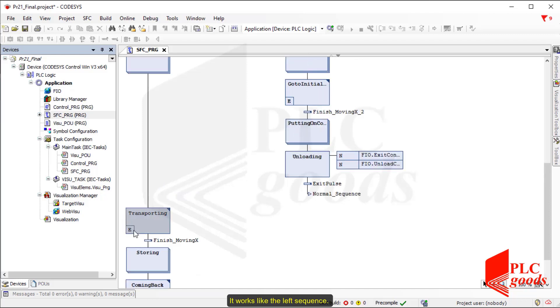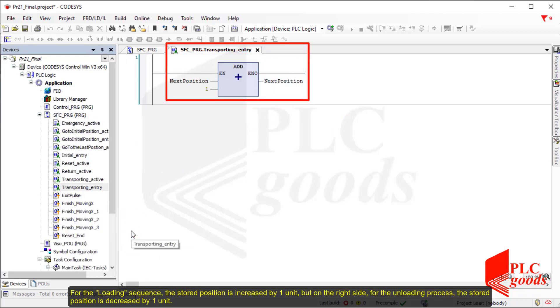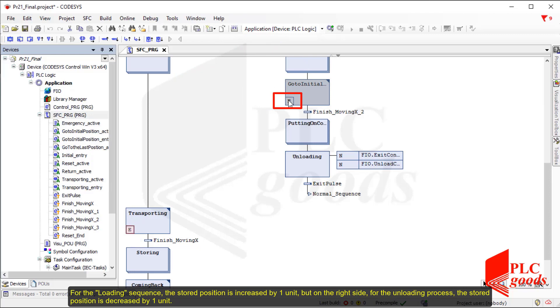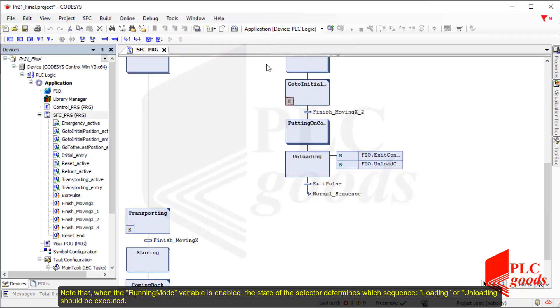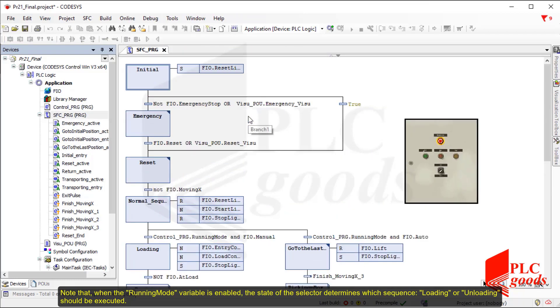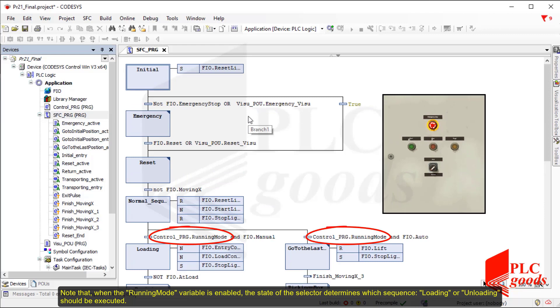The main difference is related to the entry action. For the loading sequence, the stored position is increased by one unit. But for the unloading process, the stored position is decreased by one unit. Note that when the running mode variable is enabled, the state of the selector determines which sequence — loading or unloading — should be executed.